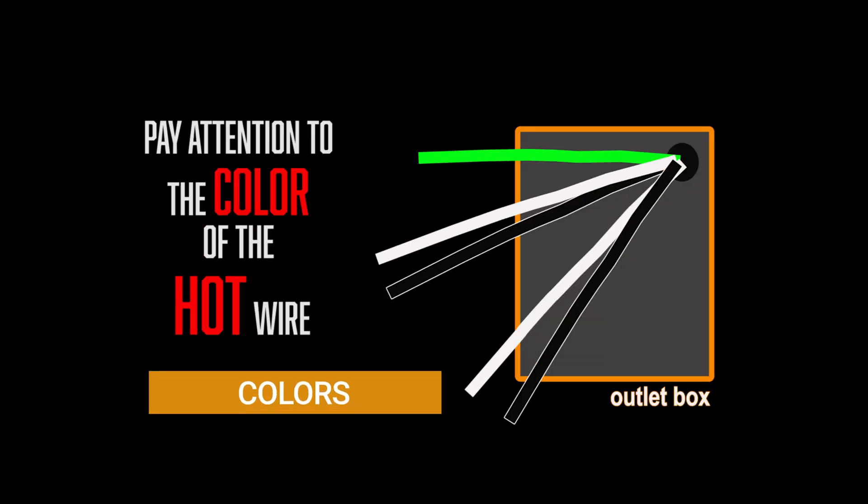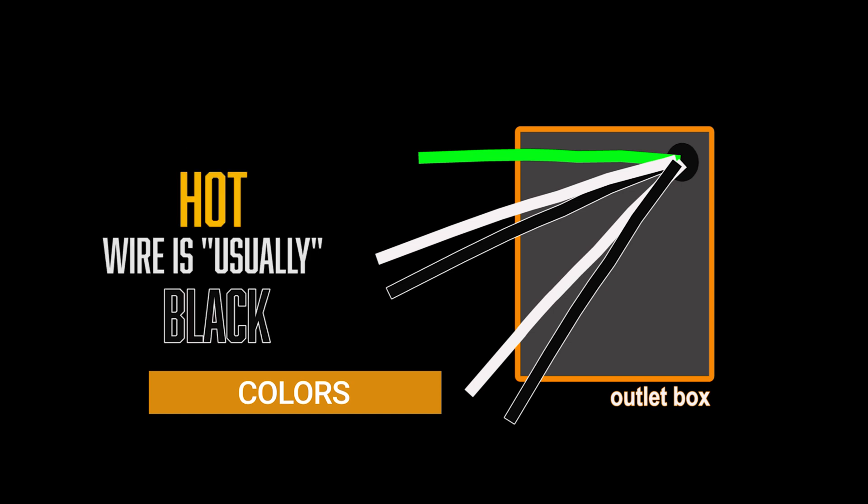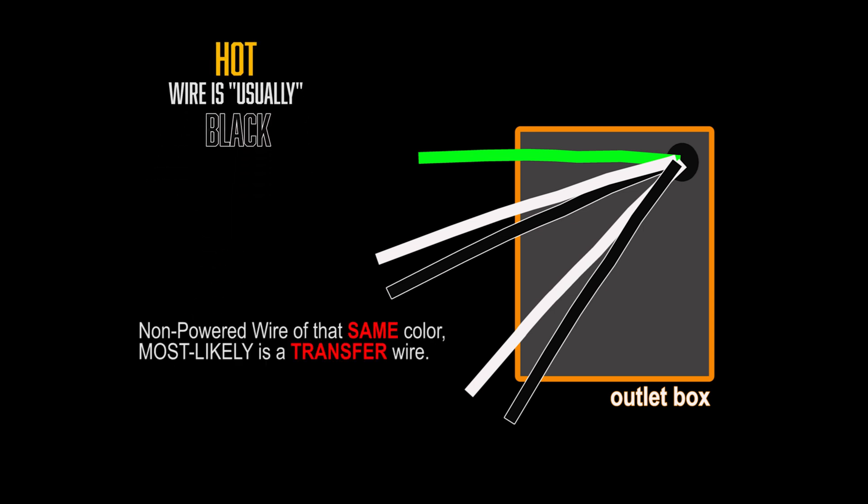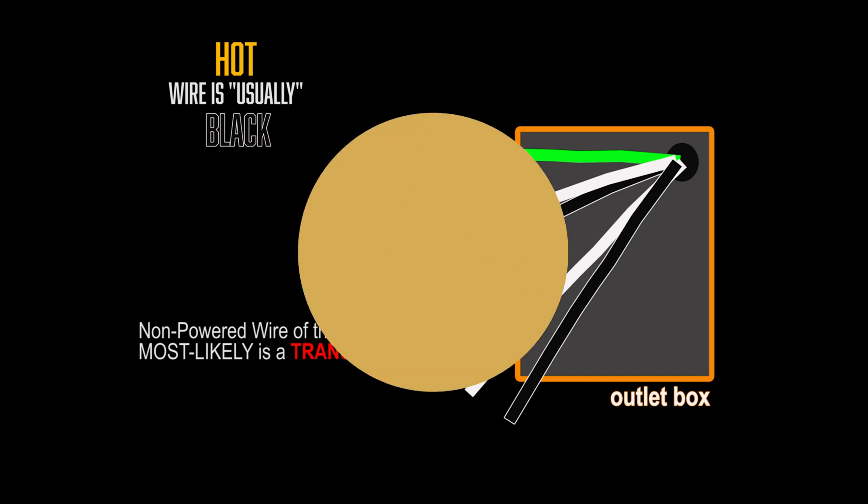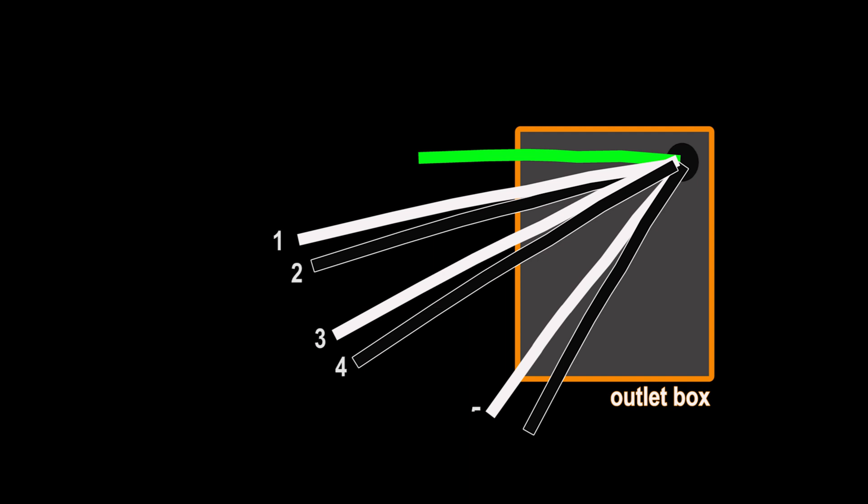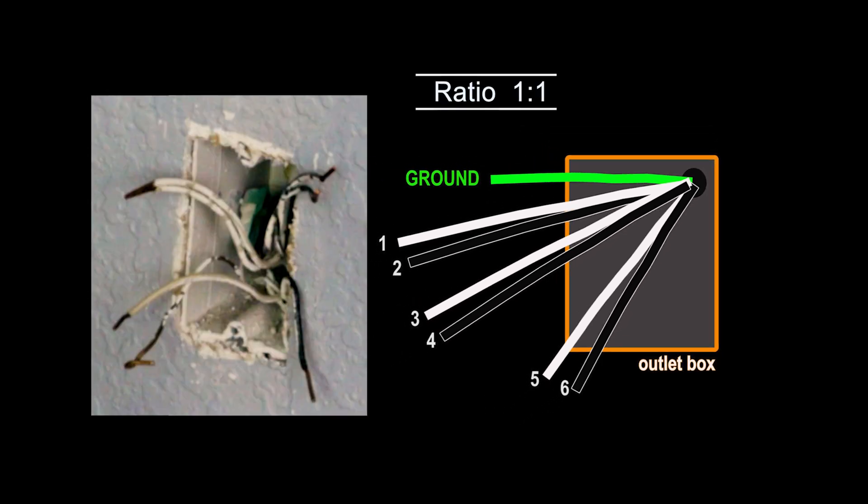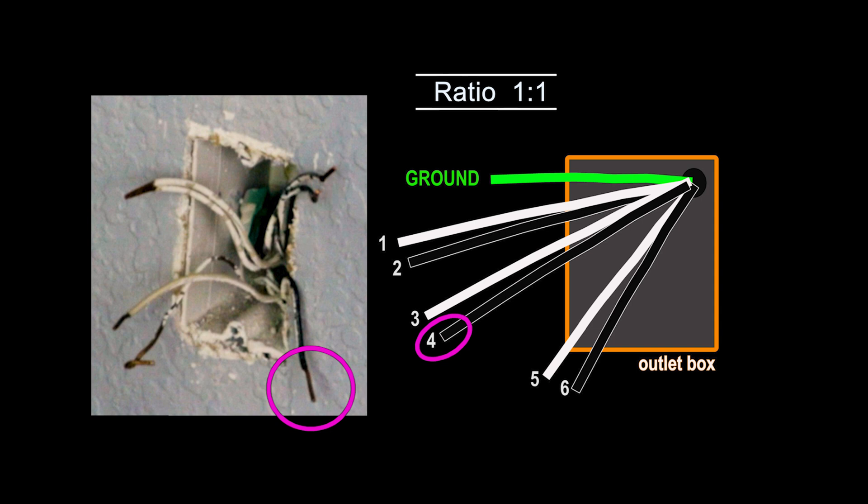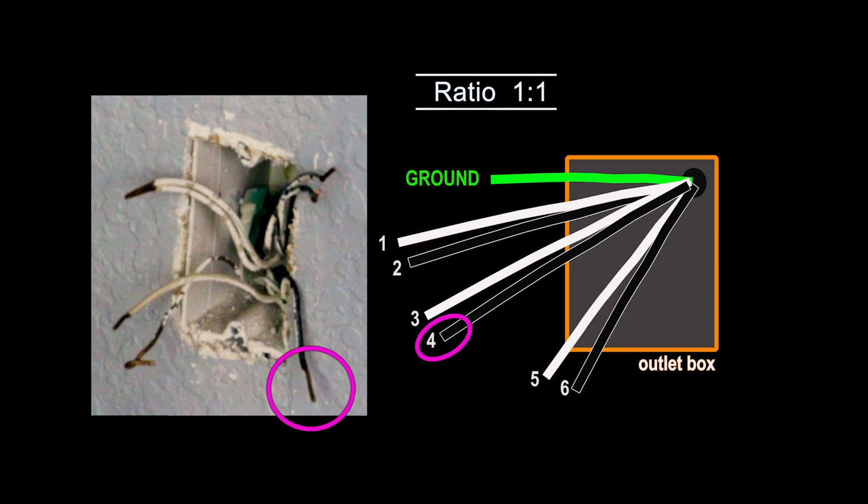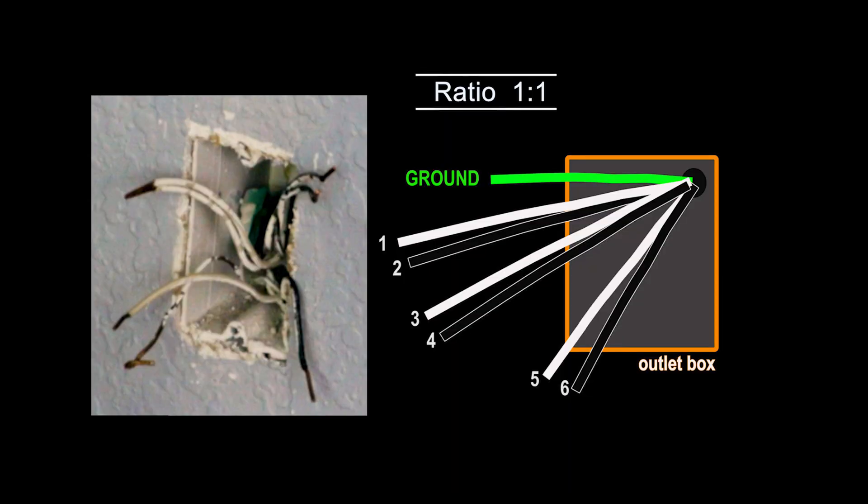If you have multiple colored wires, pay attention which one it was: black, red, white. Hot is usually black, if it's wired properly. If you have another wire of the same color, most likely it is the transfer wire that will get connected below or above your connection. In my example, I have six wires plus the ground: three white and three black and a seventh is a bare ground. If the wire color ratio is one to one, most likely you can rely on a color coding. If one of the wires turns out to be hot, the other wires of the same color are most likely transfer wires to the other devices down the line. If you look inside the box, try to see which wire is paired in sheathing with a hot one. That should be the neutral counterpart and should be of the opposite color.